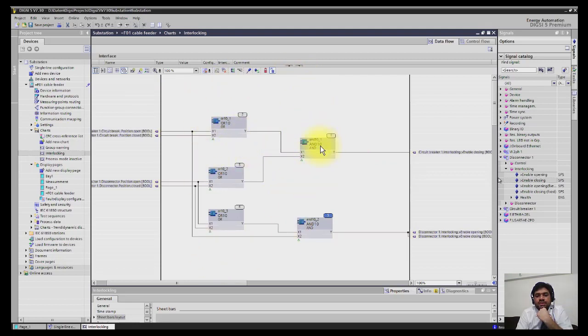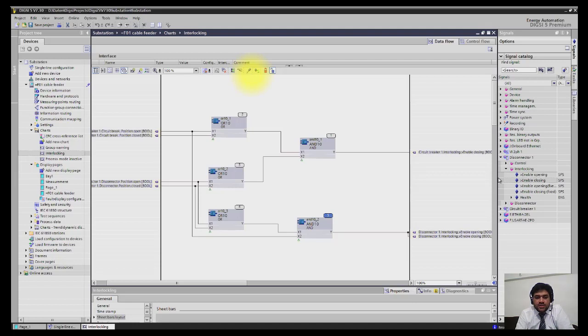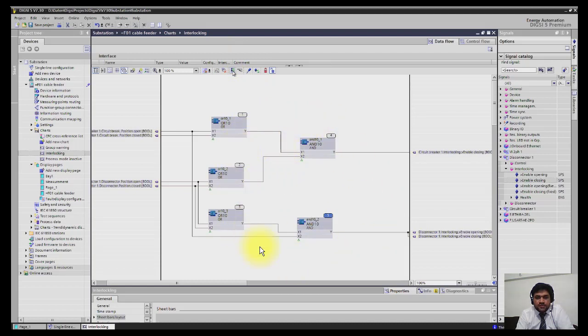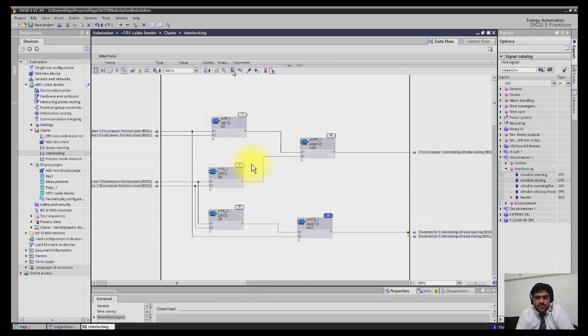It's compiling from left to right. As per this sequence it will compile this one first and then this, which may result in error. You have to optimize by clicking optimize here, and it will automatically be rearranged. Click optimize and the solution will be fixed automatically. Check here, now numbers are assigned properly. After this you have to compile the CFC chart to check and look for errors. Click here to compile the chart.